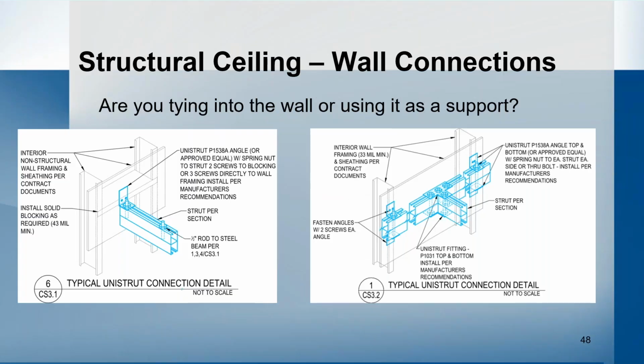And then another thing to consider is your wall connections. Typically you'll have a rod drop close to a wall, so you can just tie the end of your strut to the wall without any kind of load carrying capacity. But if load carrying capacity is required out of it, you would have to do something more like what's on the right, where the wall is actually carrying the load.